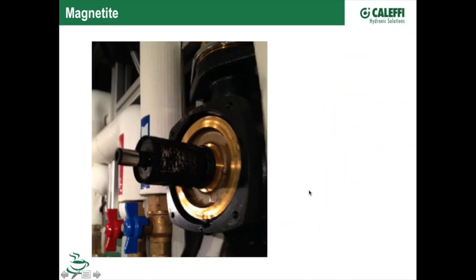This is something that's starting to become a concern in systems. This is a pump, and what we've done here is we pulled the rotor can off the outside of the rotor, and you can see there's some buildup on the outside of it. This is a strong magnet in here. This is an ECM type of pump, and you can see some deposits have collected and stuck to that magnet there. Well, what that's going to do is cause problems with the rotation of this pump, and that's in fact what happened with this. We were getting an error code that said the rotation of the pump was being impeded, and when we took it apart, we found that we had a bunch of fine magnetic particles that were stuck to this, and it was kind of jamming up that rotor, being able to spin inside there.